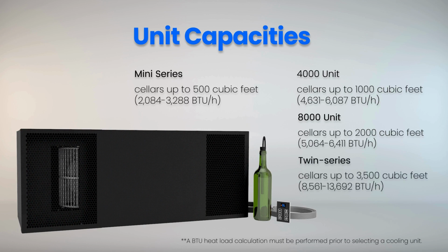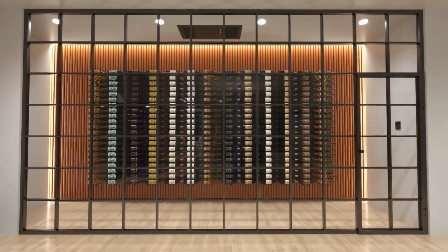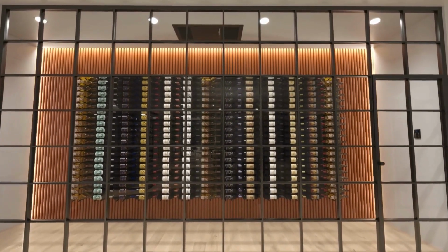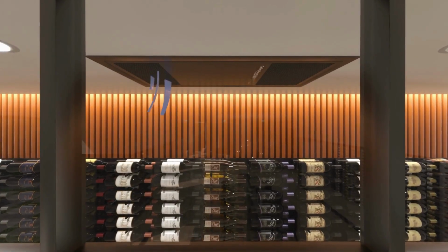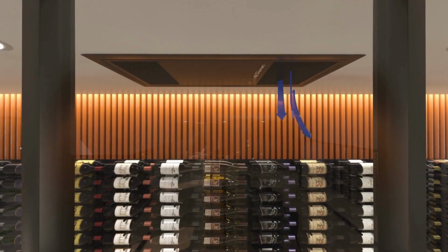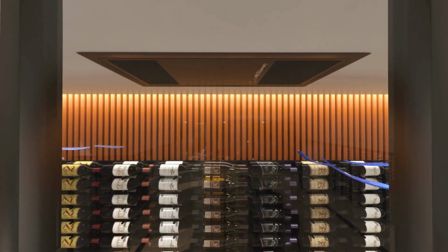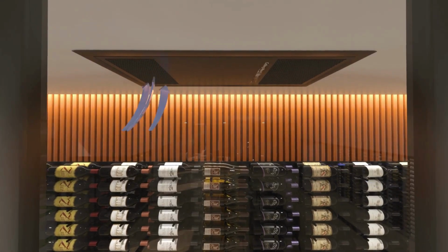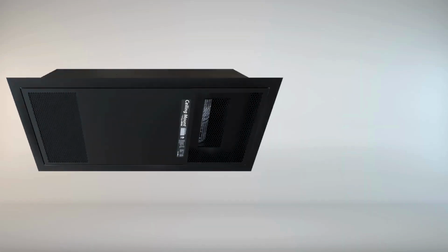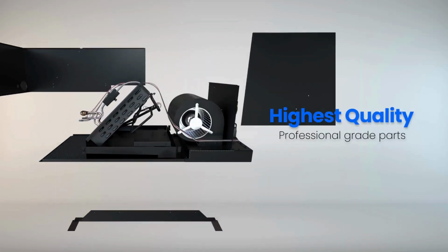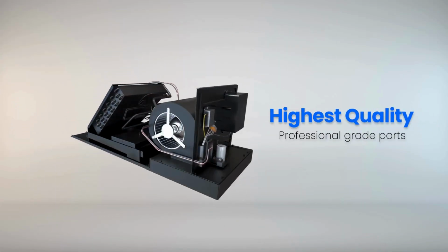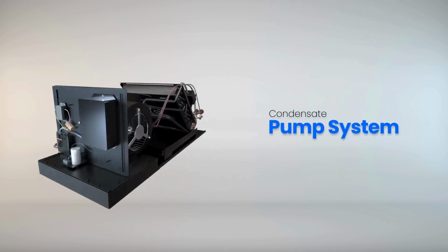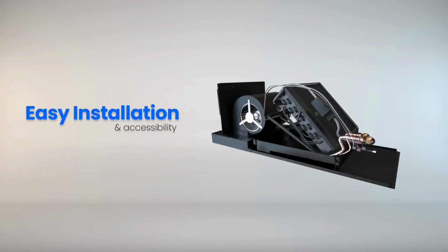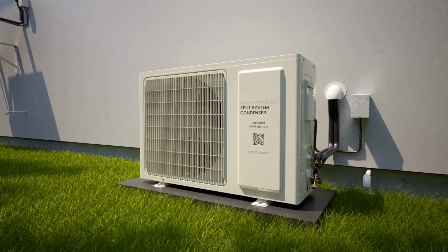BTU and heat load calculations must be performed prior to selecting a cooling unit. Utilizing our ceiling mounted evaporator has many benefits. It offers excellent efficiency by drawing in the warmer air which accumulates at the ceiling, cools and disperses the air throughout the environment. Built with the highest quality professional grade parts for longevity and performance, its design integrates a condensate pump system that is easily installed and accessible for maintenance.